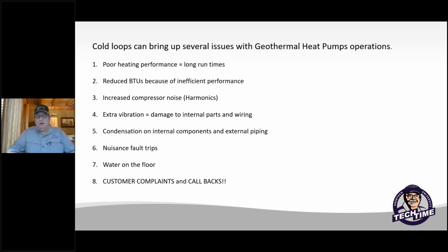The compressors run in a different envelope and may make a different noise, which sometimes irritates homeowners, and obviously we get some trouble calls that way. Vibration also changes, as part of the harmonics of the compressor. I've had refrigerant lines break, and I've had electrical wires break from the vibration. So these are all problems that can be associated with a cold loop.